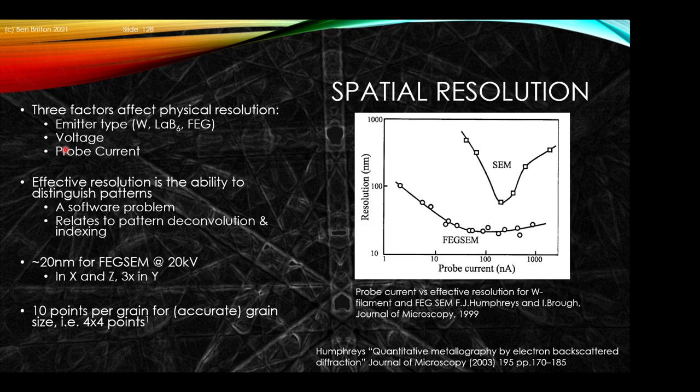Importantly, the physical resolution is where the scattering occurs, but the effective resolution is how well you can classify, index, and distinguish two diffraction patterns — that's a software problem relating to the pattern matching and deconvolution indexing routines. You can get this down to about 20 nanometers in a FEG SEM at 20 kV in X and Z, but remember it's three times elongated in Y down the tilt axis. If you want to measure grain size, think about this — you'll typically require 10 points within the grain for a relative estimation of grain size.